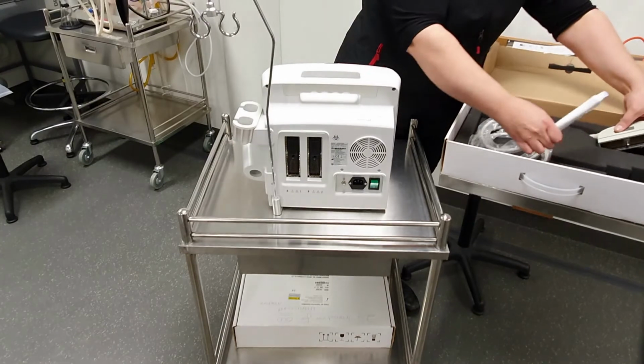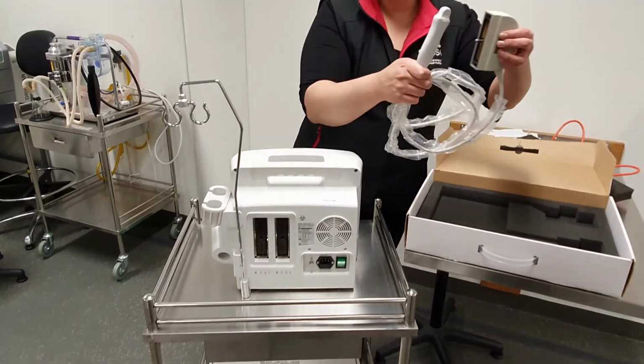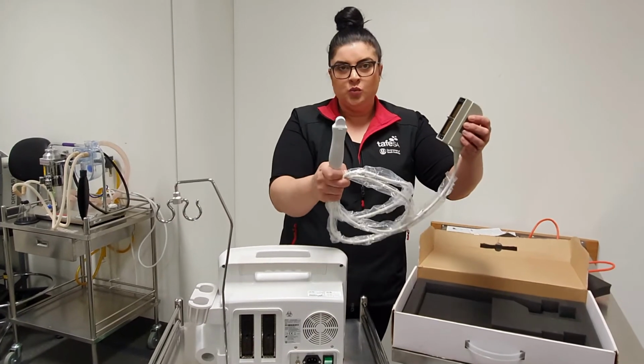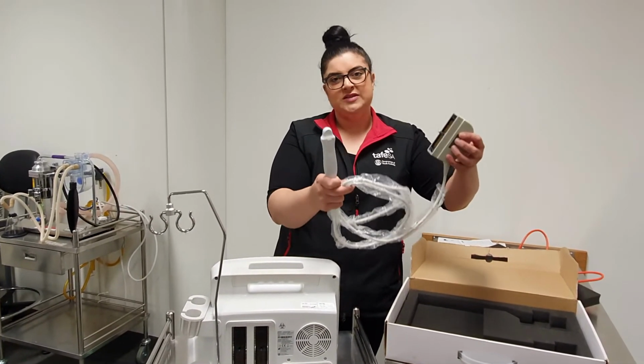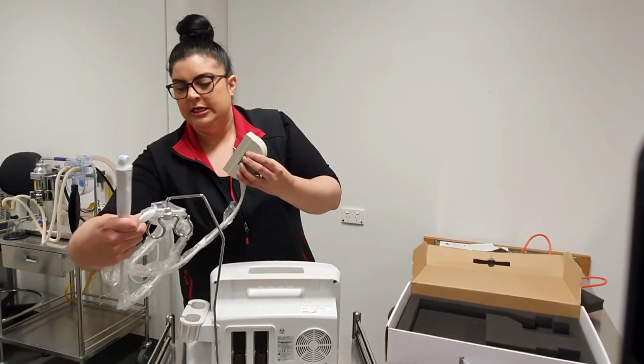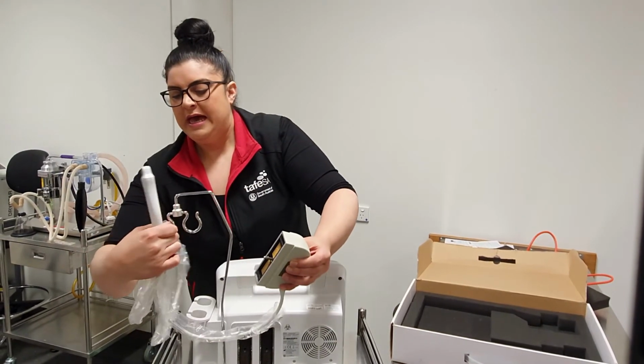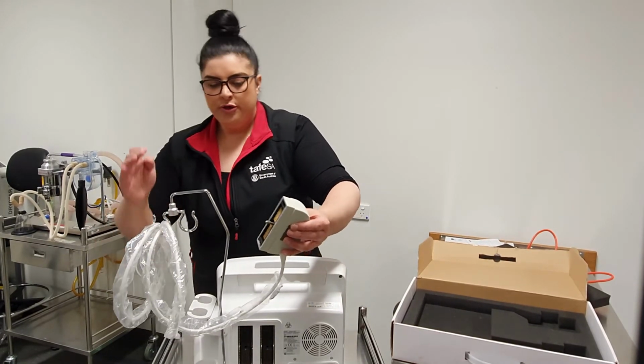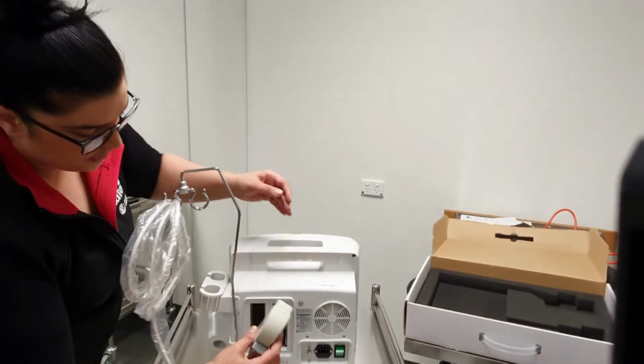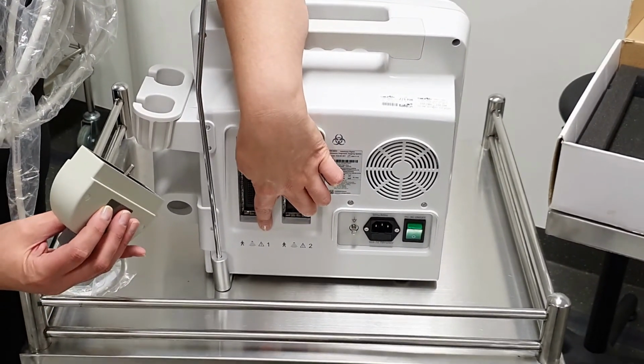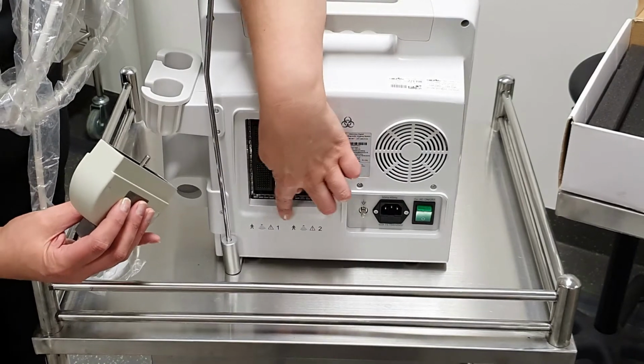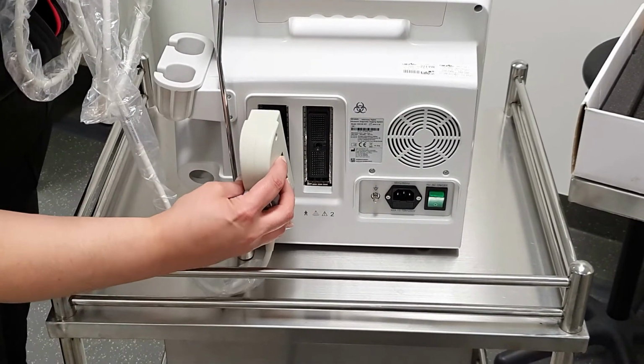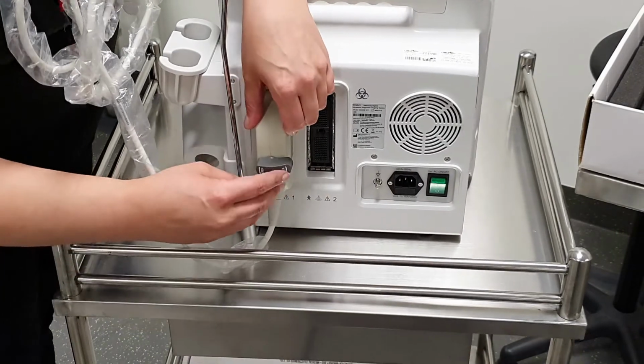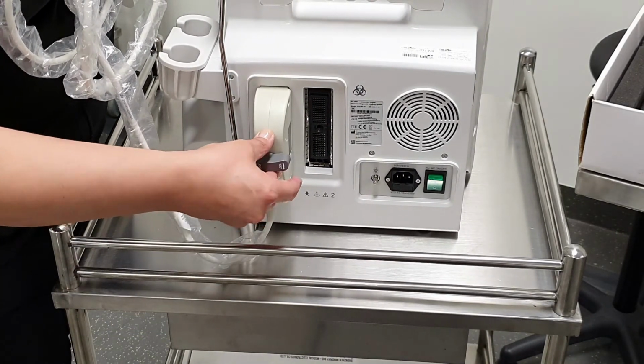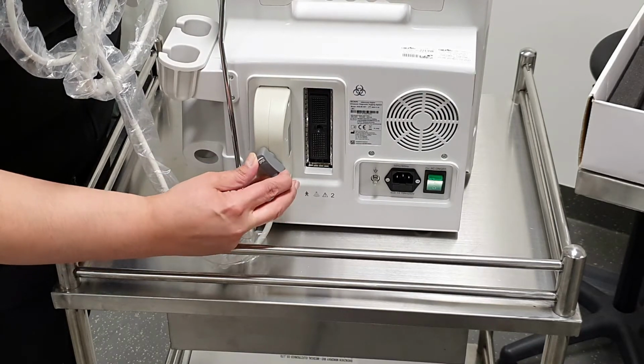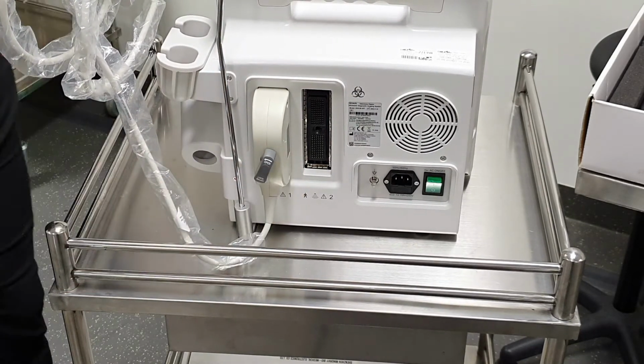I'm going to lift out my transducer, and I'm going to hold the probe and the socket at the same time, as well as the cord, so that nothing is banging into the piece of equipment. I'm going to just gently hang up the cord and the probe while I plug in the transducer, and I'm going to use socket 1. If you have more than one probe, use both. If you only have one, use socket number 1. I'm going to place that in. I'm going to put gentle pressure on the probe against the machine, and then I'm going to turn this lock. Okay, and that will keep that in place.